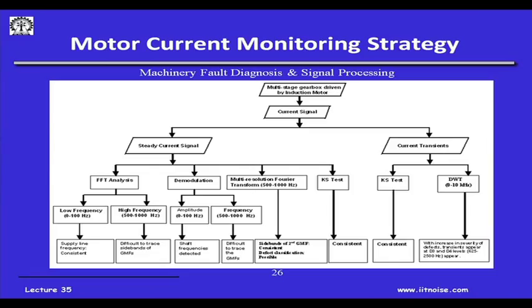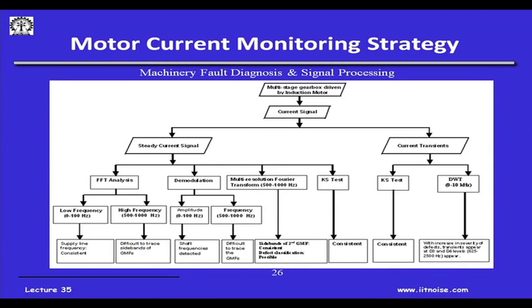In earlier classes I talked about fault prognosis on a lathe machine, where we monitored the motor current while cutting aluminum and steel. This was about 15 years ago. We found that the current in the lathe machine changes when it machines steel versus aluminum, and that this current definitely carries information about the load on the lathe spindle. A defect also gives a load, and that load will reflect in the current. So by monitoring and analyzing the current we can find out faults — in this case the gear box, and in the previous case the lathe machine.